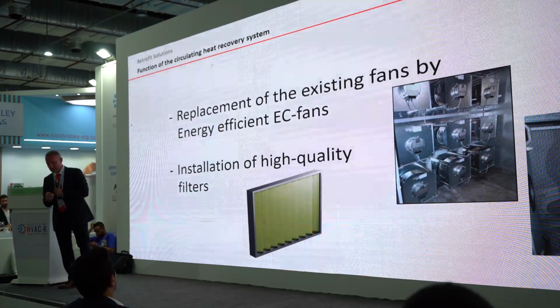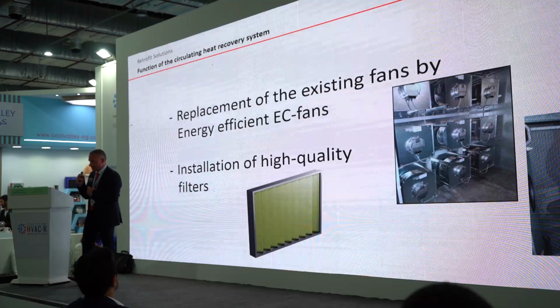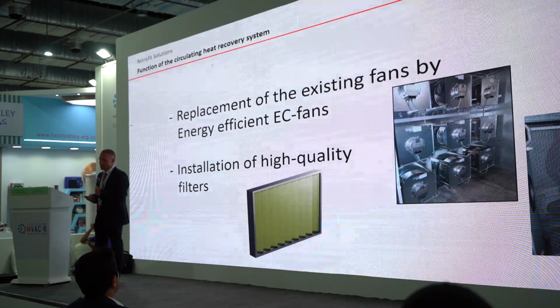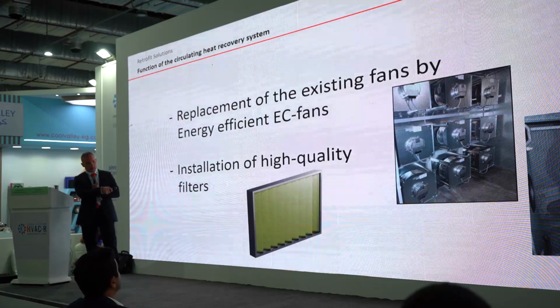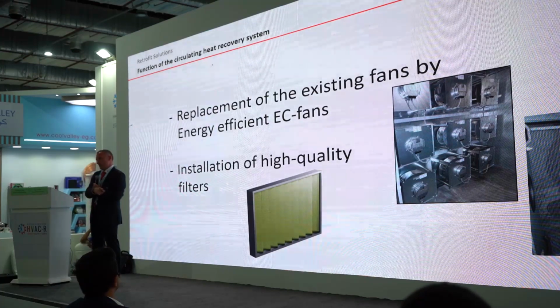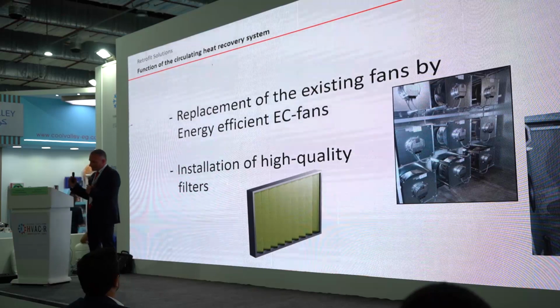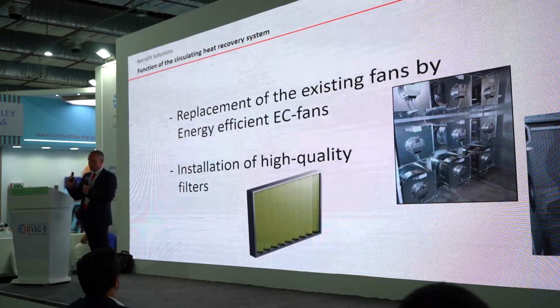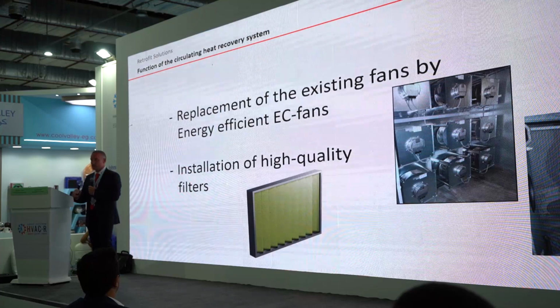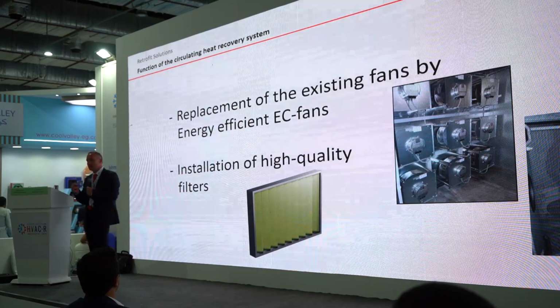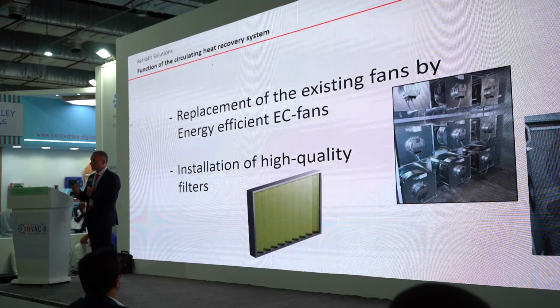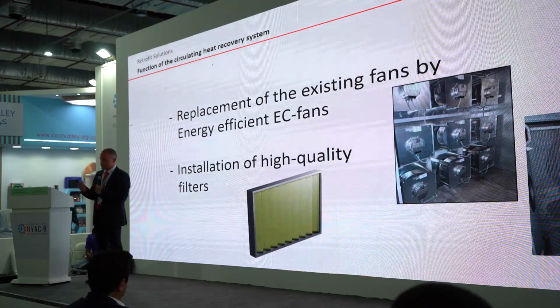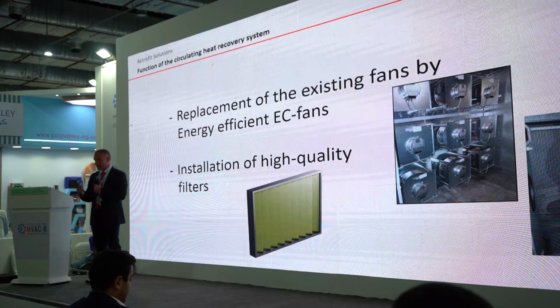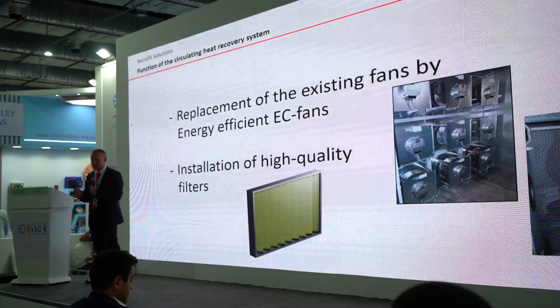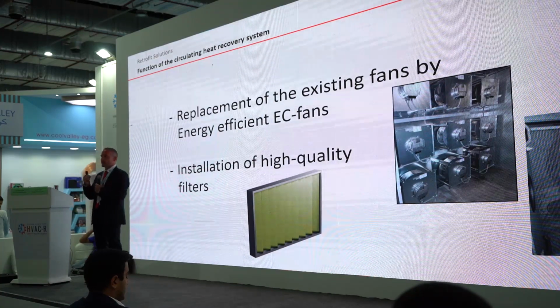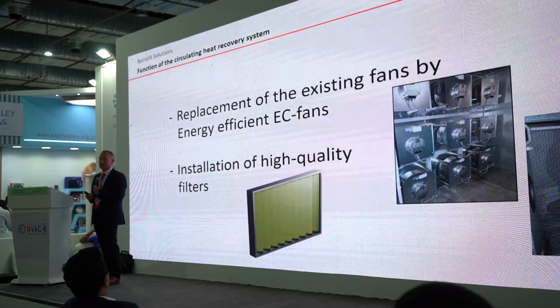At the beginning of the presentation, I said reducing the pressure is one key to reduce energy consumption. This also applies to filters. If you go to a high quality filter, you have lower pressure losses. At the beginning you have more investment because the filters are more costly, but if you save 10, 20, 30 Pascal, you have to calculate it, it brings you a huge benefit.